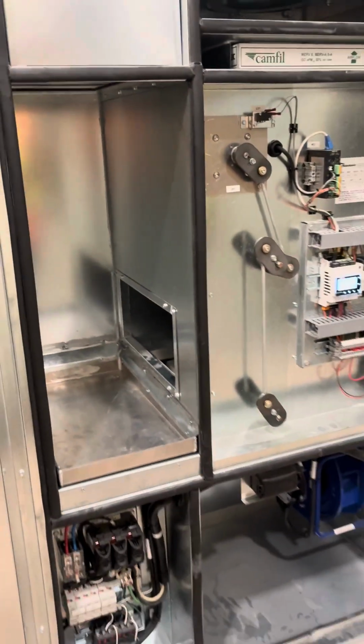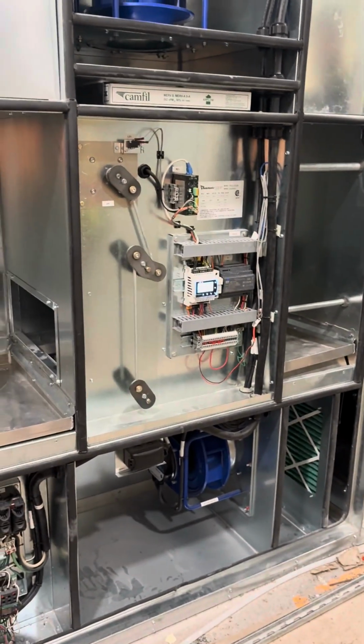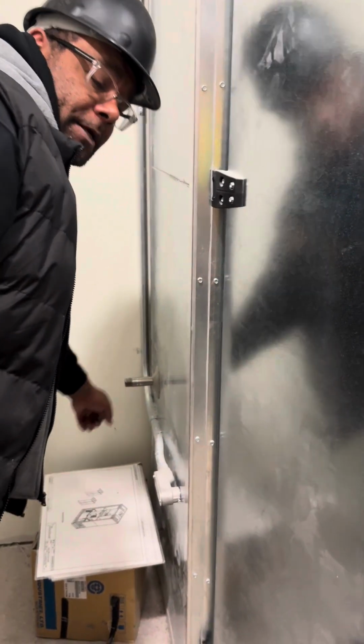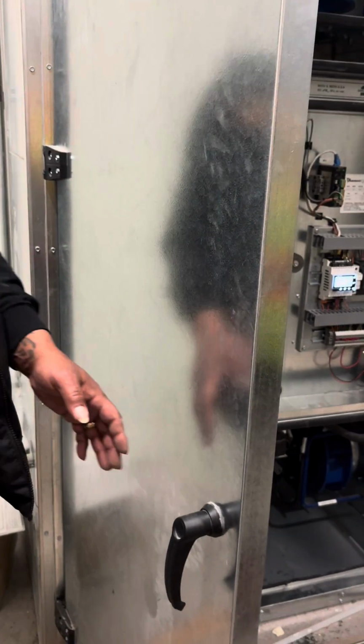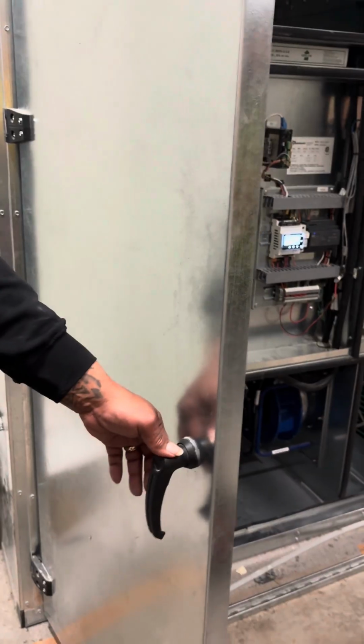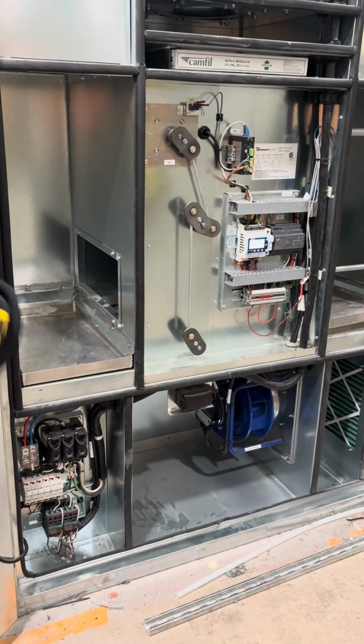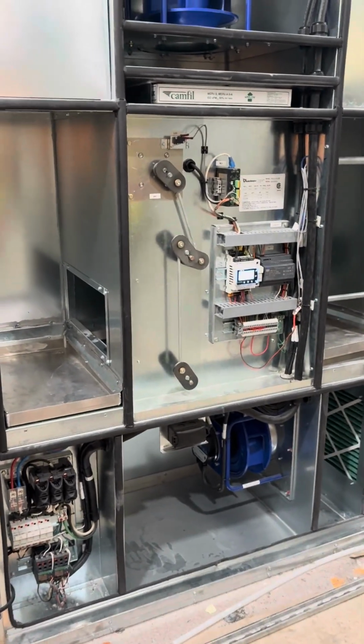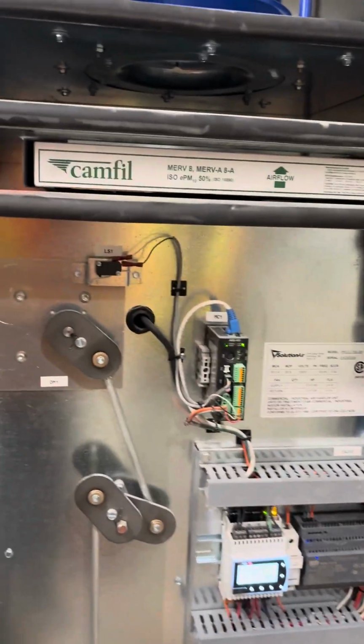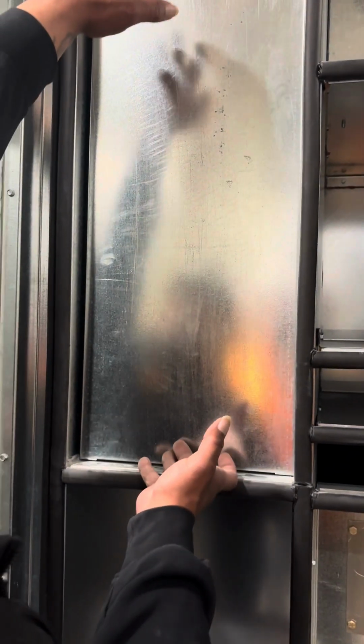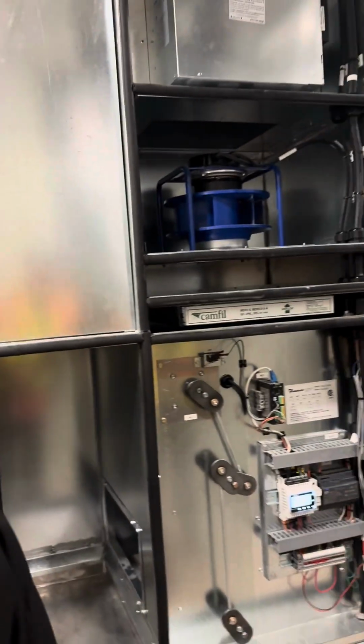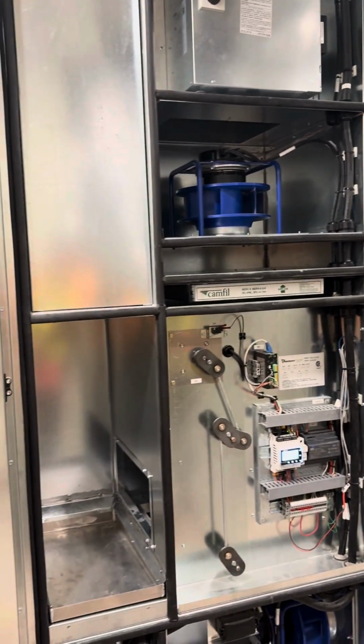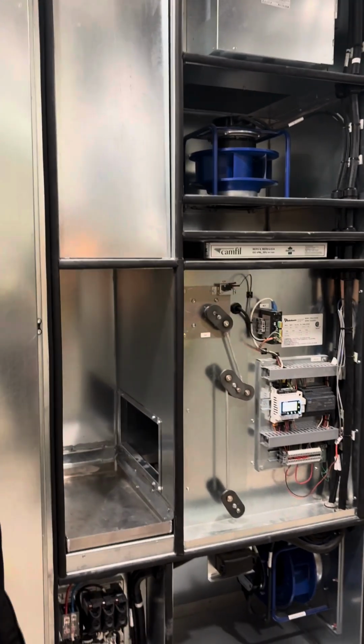When you clean the internals, you hook up hoses to the two drain pan connections, which are here. I'm going to put caps on them, but if you feel the need to clean the inside with spray, water, hose, you'll be able to do so, and it will drain out to wherever the drain is. Yeah, you've got to hook it, pull it out. The whole core will slide out. There'll be multiple cores in there. There's no locker, they're just sliding cores. And again, the IOMs will show you the procedure on how to do that.